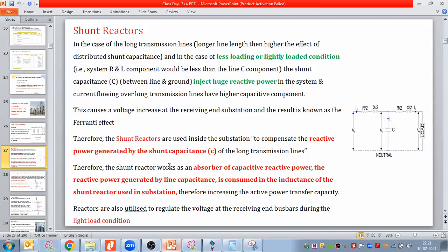Shunt reactor or inductor works as an absorber of the capacitive reactive power. The reactive power generated by the line capacitance is consumed by the inductance of the shunt reactor used in the substations, therefore increasing the active power transfer capacity. Reactors are also utilized to regulate voltage at the receiving end substation busbar during light load conditions.